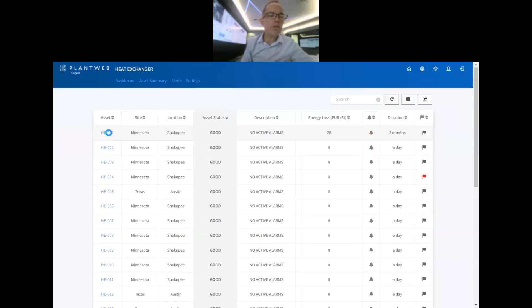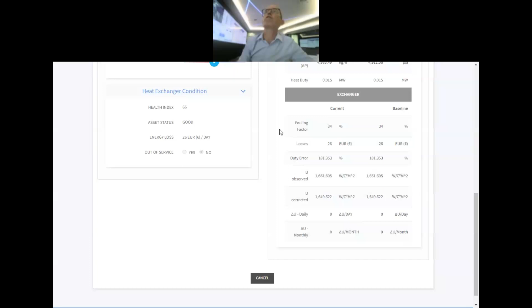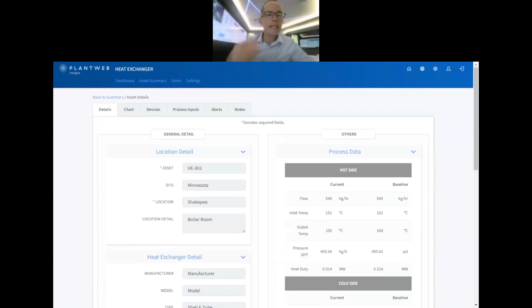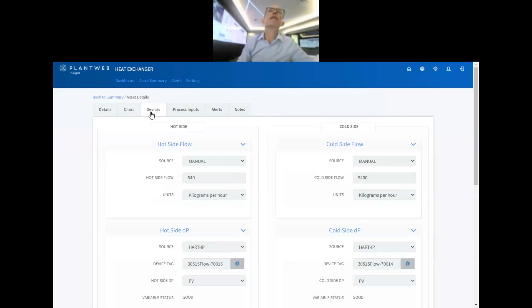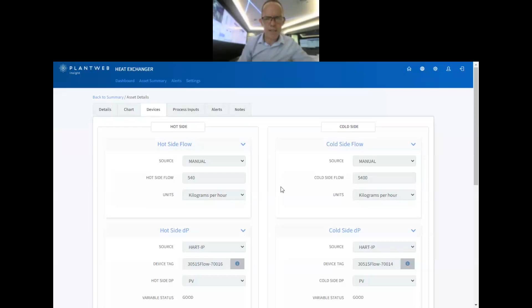So now we can take the opportunity to zoom into one of these. If I go down to the bottom, I can see the fouling factor, the losses, the duty, and the change in heat transfer coefficient, etc. All of that information is now calculated for me, bringing in data from the underlying sensors. On this page you can see the various sensors where the data comes in, and here, through the wireless HART sensor.